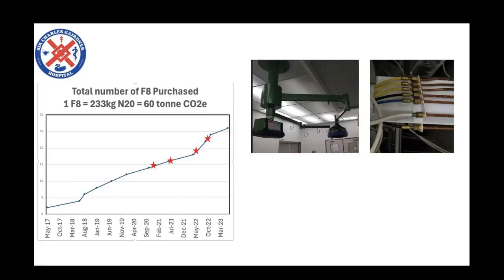And they leak because they're meant to get serviced or looked at least once a year, and they should be serviced every 4 years, and every 10 years, all the pipes should be changed. I'm pretty confident that the Sir Charles Gairdner pendants had never been serviced since they were installed somewhere in the late 70s. And actually, if you ask around engineers around the country or hospitals, it's very hard to find anyone who will admit that they've ever serviced a pendant, because they're very difficult to service. And if you open them in WA anyway, the opinion is that's like opening the roof space, and you need to do 5 days of cleaning your theatres after opening the roof space. So hospitals don't sign off to get them serviced because it means shutting down the theatre for 5 days.